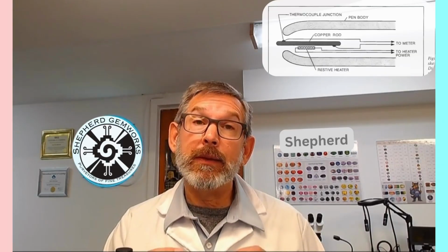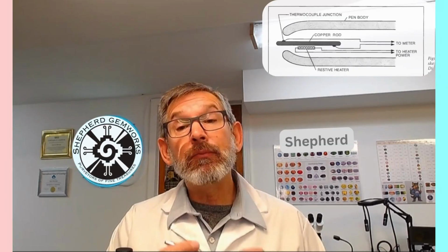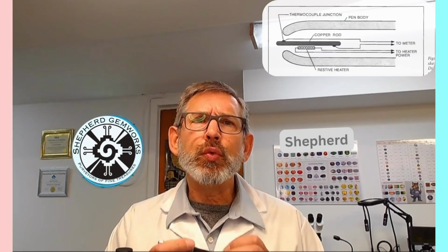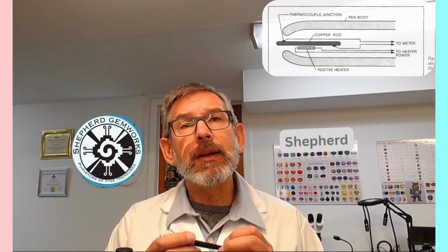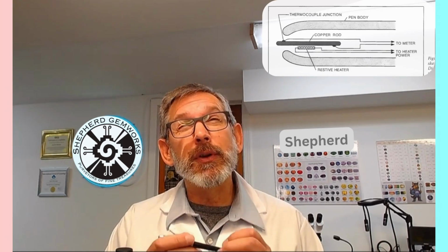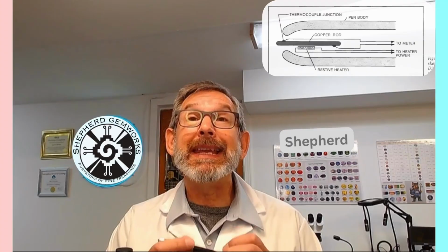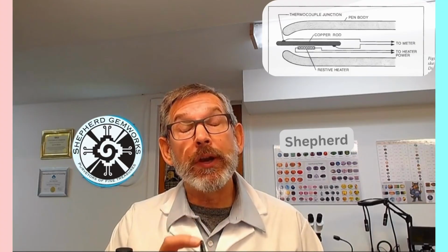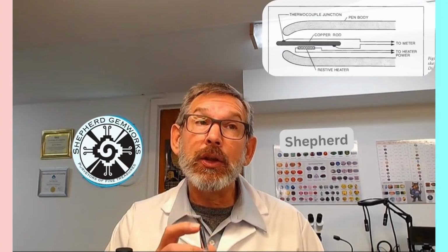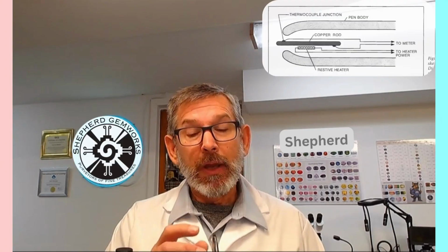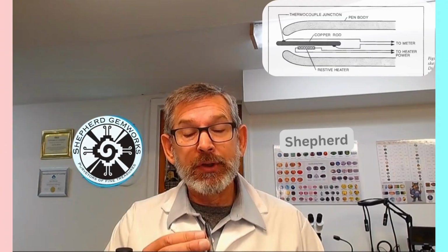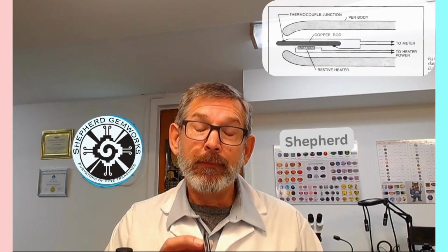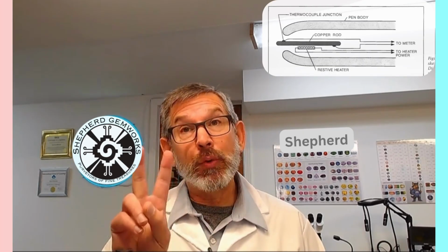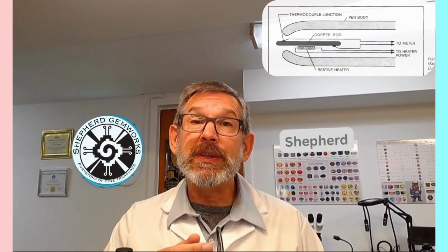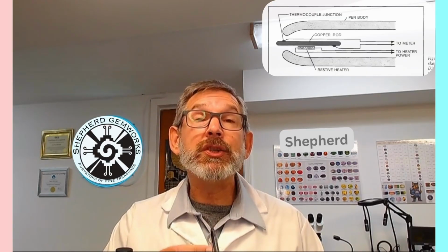The probe in the PGT2 uses a resistive heater. A 22 ohm resistor operating at approximately 2 volts delivers 0.18 watts of heat, or about 0.043 calories per second. A type T thermocouple, which is a copper constantan thermocouple, uses the temperature difference between two junctions, and this produces a voltage signal, which the device interprets to estimate thermal conductivity.